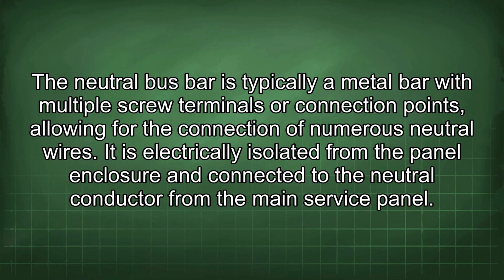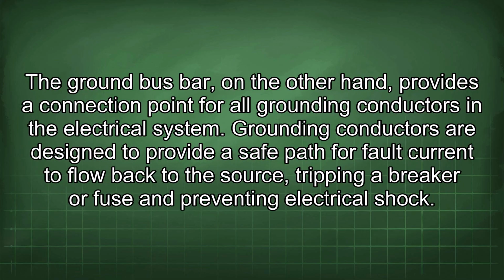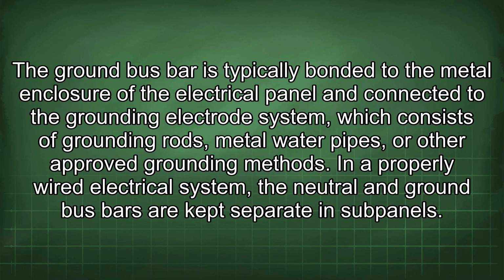The ground bus bar, on the other hand, provides a connection point for all grounding conductors in the electrical system. Grounding conductors are designed to provide a safe path for fault current to flow back to the source, tripping a breaker or fuse and preventing electrical shock. The ground bus bar is typically bonded to the metal enclosure of the electrical panel and connected to the grounding electrode system, which consists of grounding rods, metal water pipes, or other approved grounding methods.